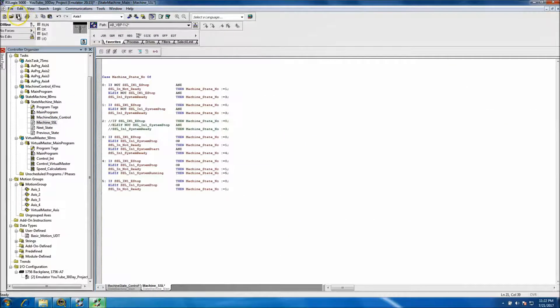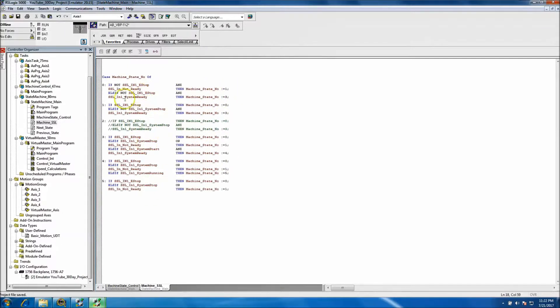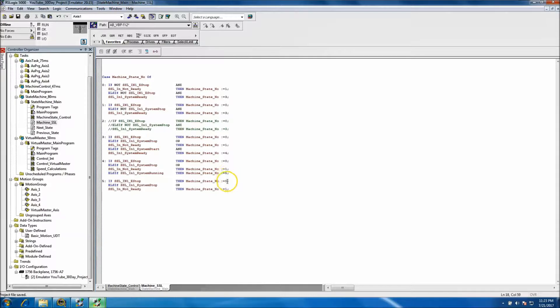This is the full logic feeding into the state machine array. We'll pop that back open, hit save, and come back to throw descriptors in on the next video. This is a good representation of a CASE scenario — you say CASE OF and still use IF/THEN/ELSE. It's a really good way to index through the whole state machine and know exactly where you're at: State 0 can go to 1 or 3; State 1 can go to 3; State 3 can go to 0, 1, or 4; State 4 can go to 0, 1, or 5; State 5 can go to 0 or 1.